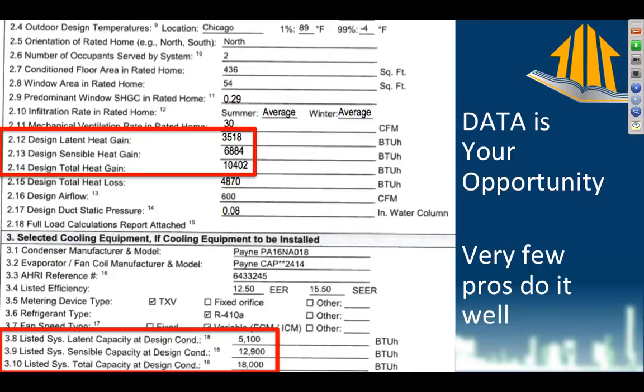Since we have a 500 square foot apartment, we have a very low load, and unfortunately, what you see there at the very bottom with the listed system total capacity at design conditions is 18,000 BTUs per hour. You can see that that's about double the size of what we need. The problem here is that our tiny little apartment is too small for the smallest split system that they make. So the very smallest split system air conditioner that they will manufacture for you is 1.5 tons. A ton being 12,000 BTUs per hour, 18,000 would be 1.5 tons. So that's the smallest that we can go. So it really doesn't matter whether it's 10,000, 12,000, 14,000, 16,000, or 18,000.